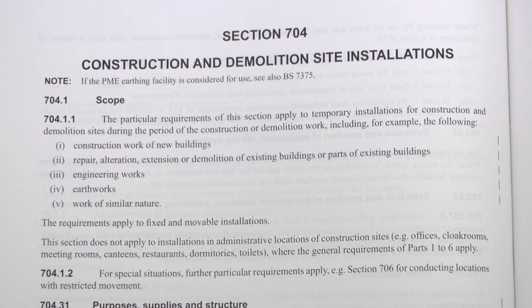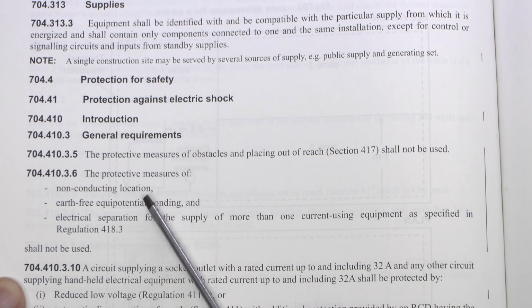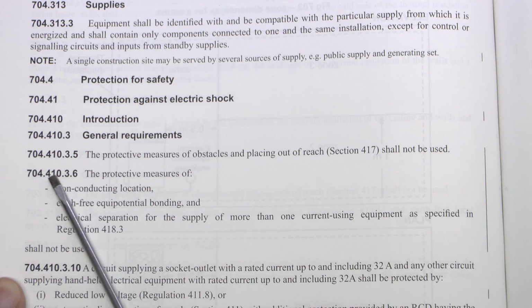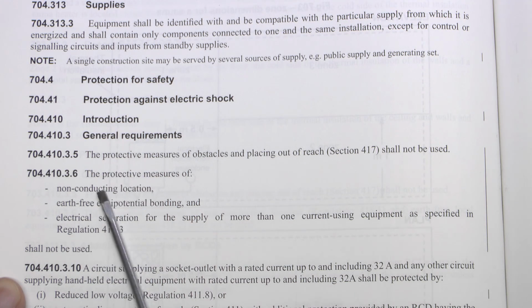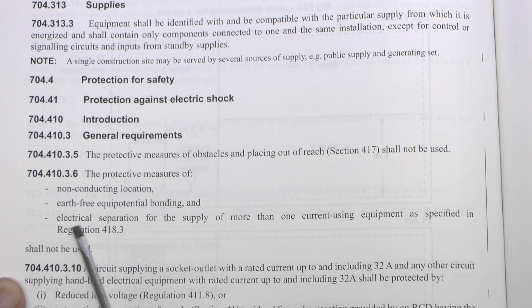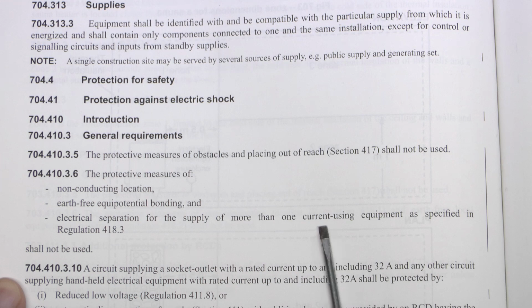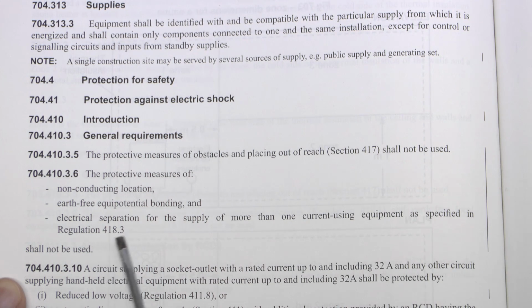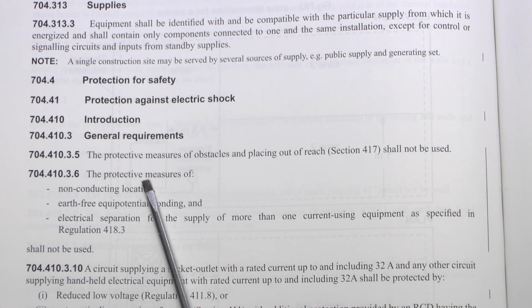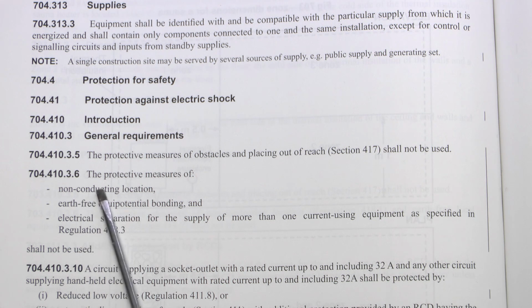And just a few changes in this one. We have the first addition here, which is in 704.410.3.6, protective measures. The one that's been added is electrical separation for the supply of more than one current using equipment as specified in Regulation 418.3. Essentially these are things which shall not be used. So as well as the other two, now we've got this electrical separation, which can't be used either.